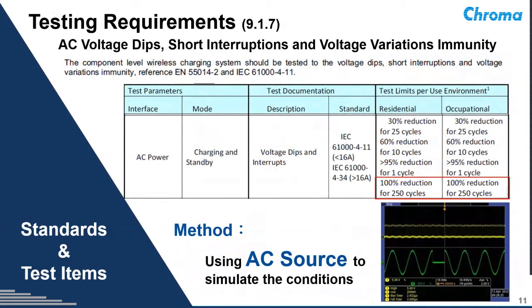For SAE J2954, chapter 9.1.7, the test requirement defines that the component level of a wireless charging system should be tested for voltage dips, short interruptions, and voltage variation immunity to comply with EN 55014-2 and IEC 61000-4-11. You can see the table lists what type of requirement the SAE paper lists. And we can use the AC source to simulate the conditions.